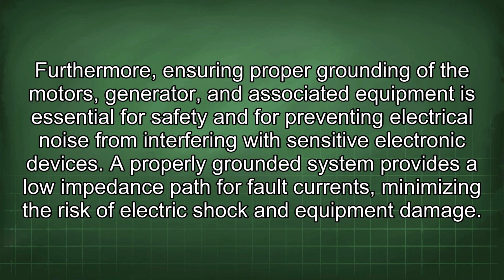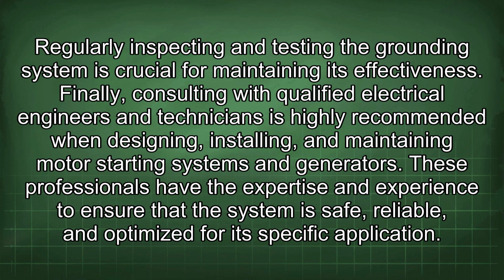Furthermore, ensuring proper grounding of the motors, generator, and associated equipment is essential for safety and for preventing electrical noise from interfering with sensitive electronic devices. A properly grounded system provides a low impedance path for fault currents, minimizing the risk of electric shock and equipment damage. Regularly inspecting and testing the grounding system is crucial for maintaining its effectiveness.